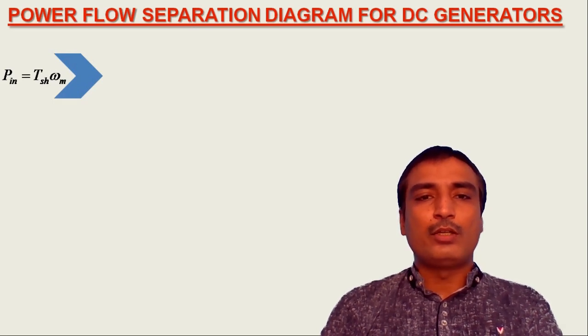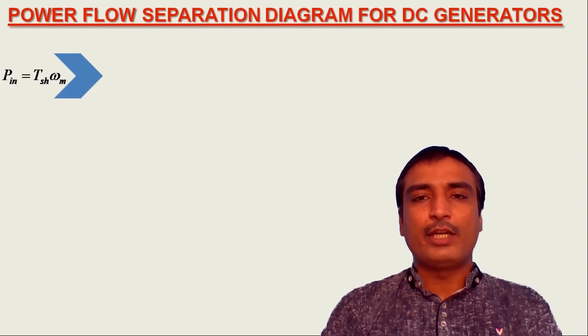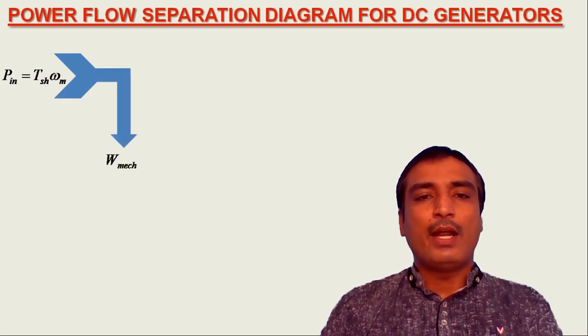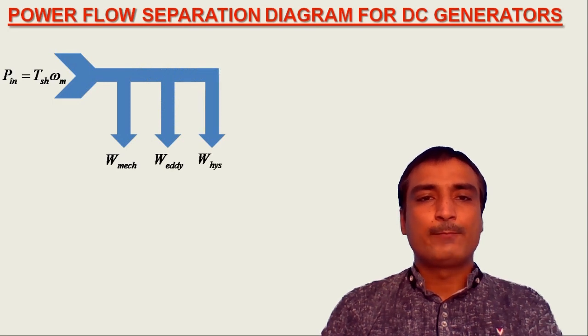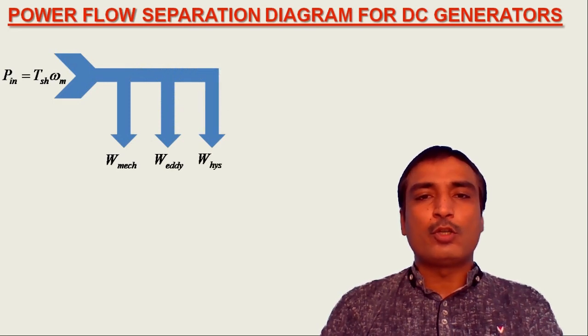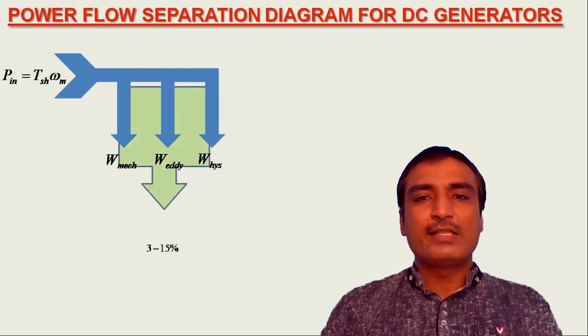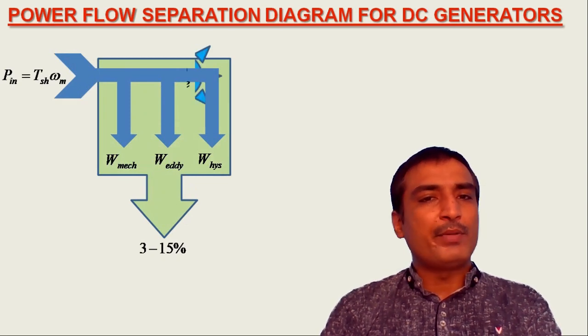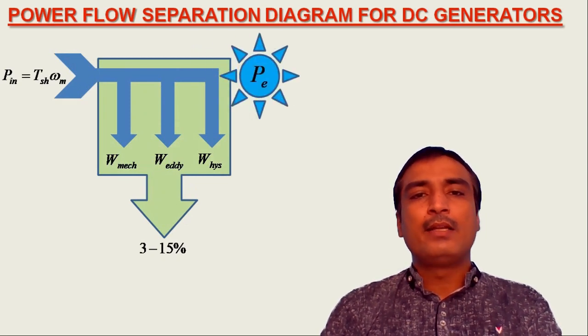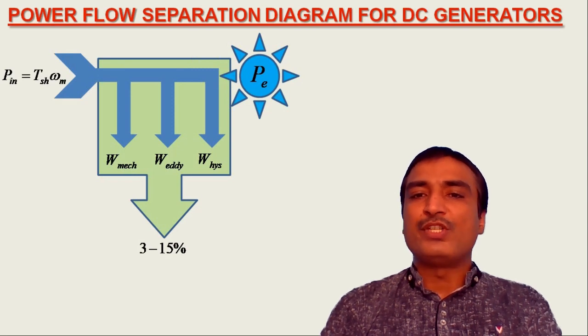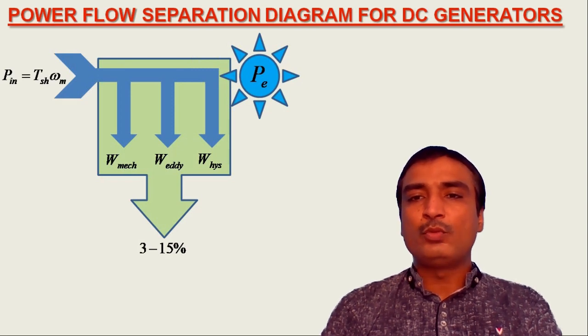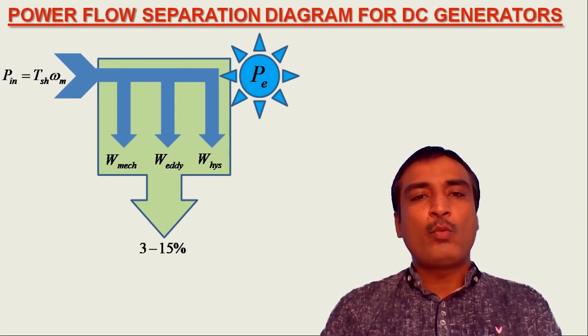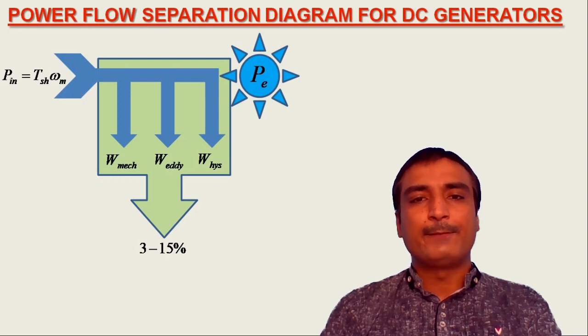These rotational losses occurring in the DC generator include mechanical losses, eddy current loss and hysteresis loss. Now, after subtracting these rotational losses from the mechanical input power, what remains is represented as the net mechanical power, which is then converted to electrical power by electromechanical energy conversion.